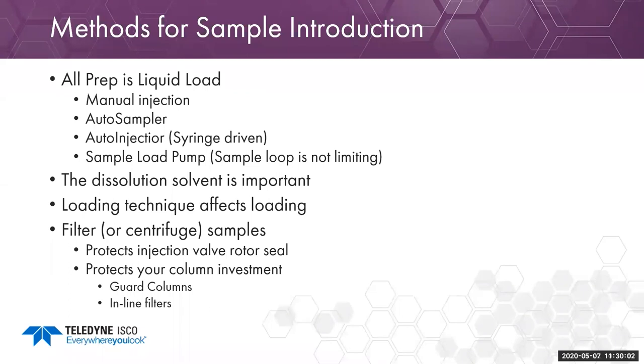The dissolution solvent is one of the most critical choices you can make for your chromatography. The loading technique affects your loading: the auto injector allows multiple injections; the sample load pump handles large volumes of dilute sample; manual injection is limited to your syringe size. One of the most important sample prep steps is to filter or centrifuge samples. This protects the system at the injection valve rotor seal interface and, more importantly, protects your column investment by preventing particulates from collecting on the column frit over time.